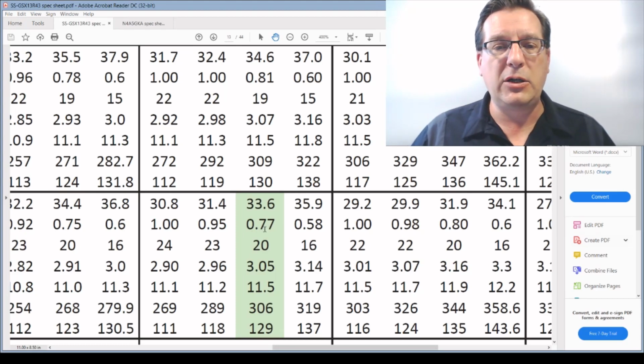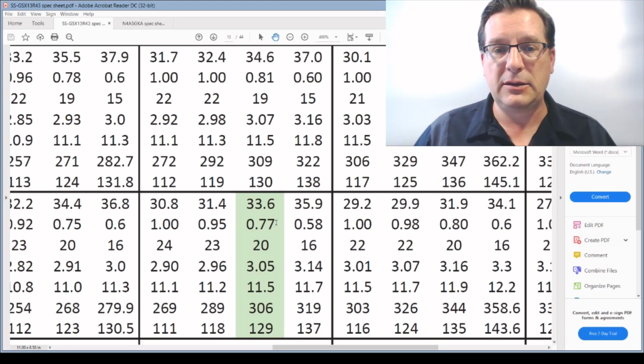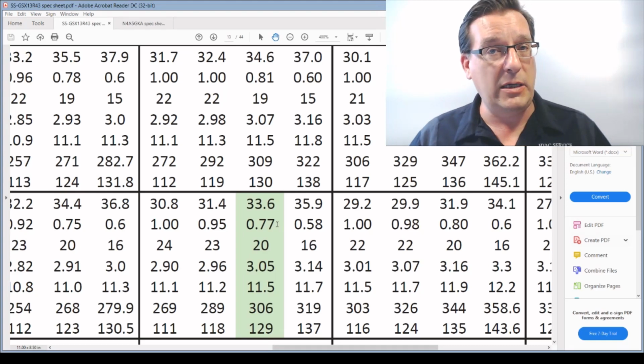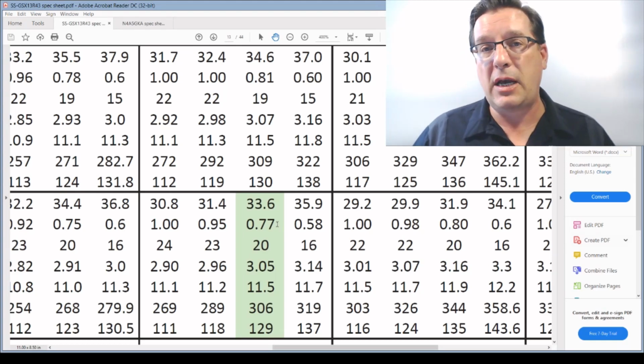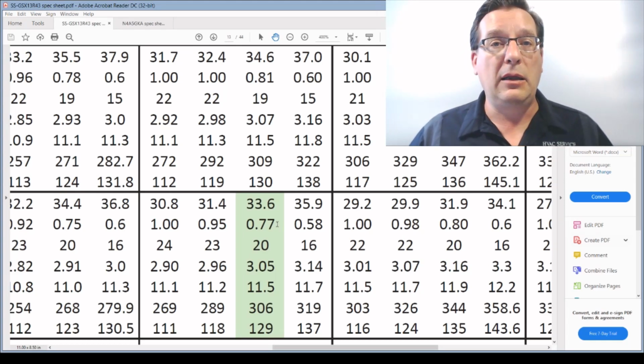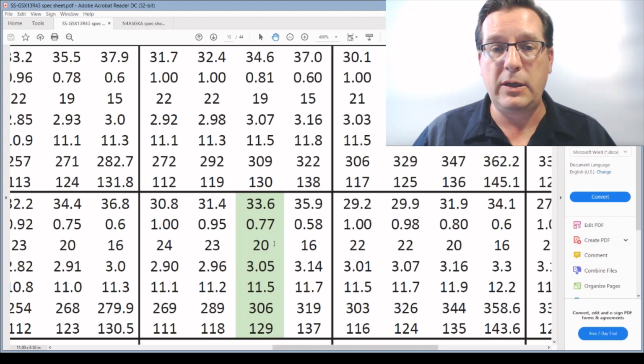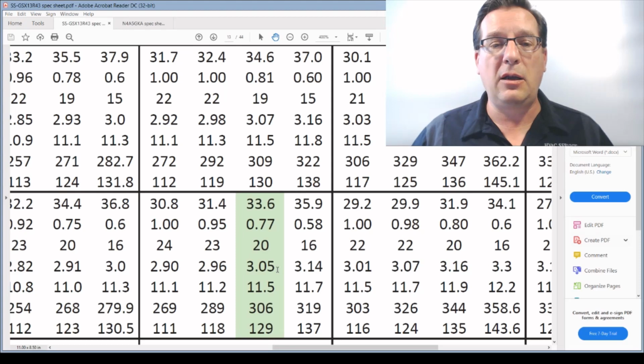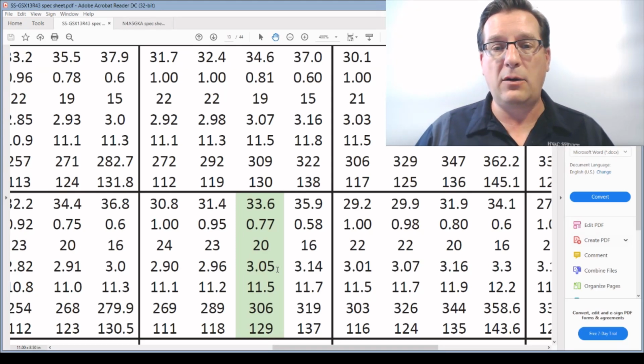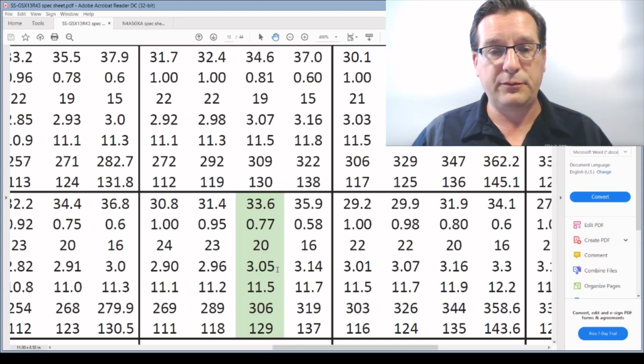Our sensible heat ratio is 77% of those BTUs are going to be sensible BTU. The remaining 23% are going to be latent heat BTUs. The temperature drop will be 20 degrees. The kilowatts consumed are going to be 3.05 kW or 3,500 watts, 11.5 amps, 306 pound head pressure, 129 pound suction pressure.